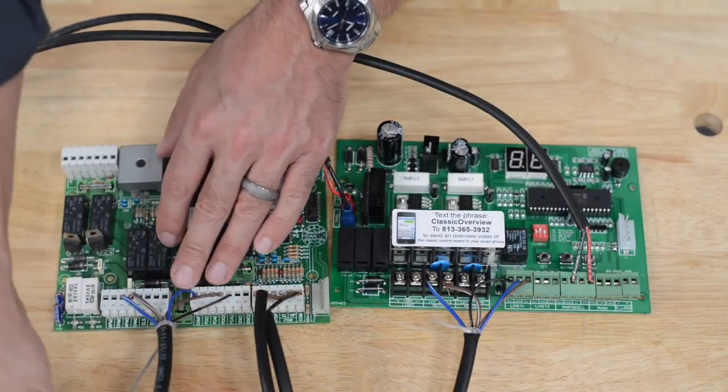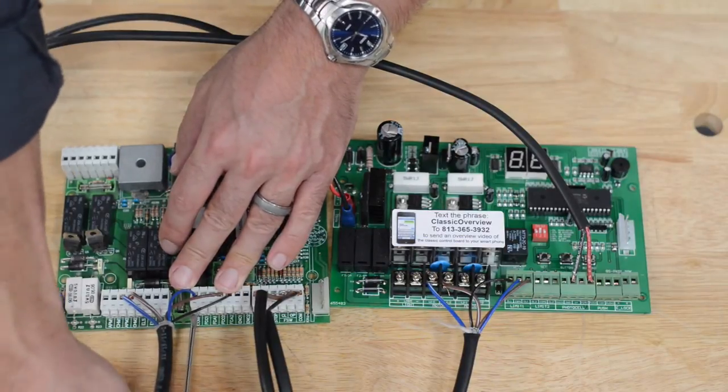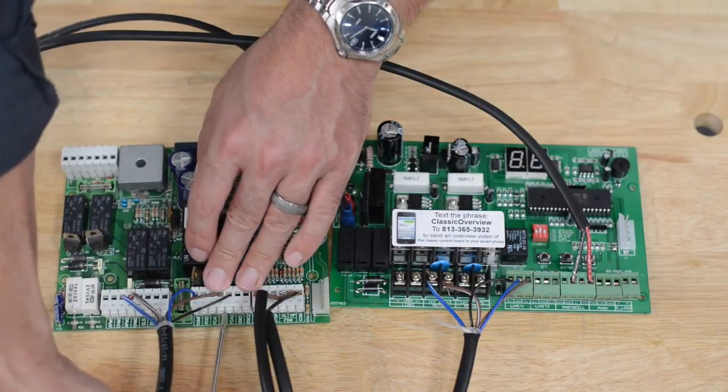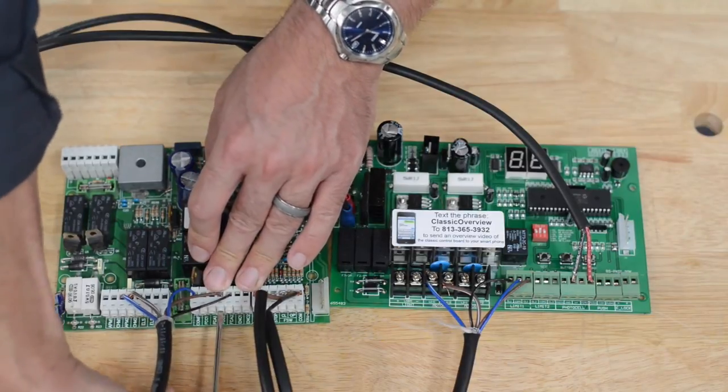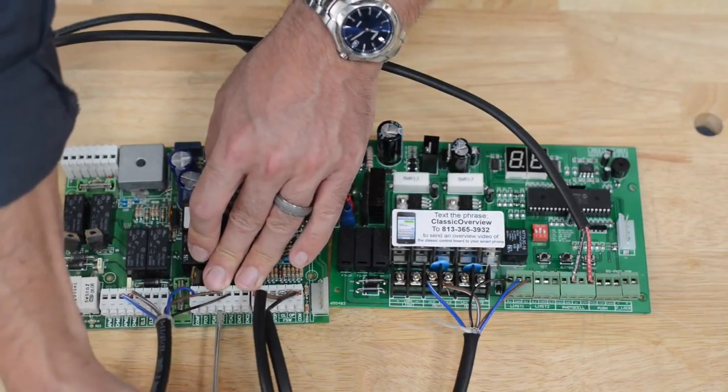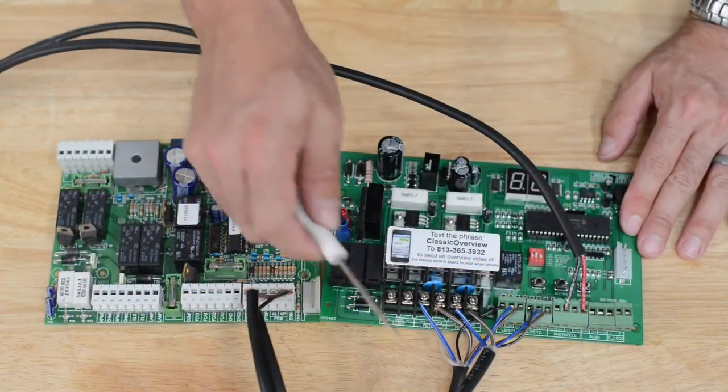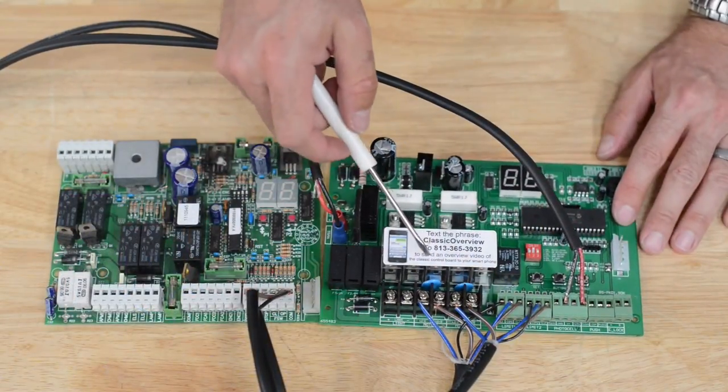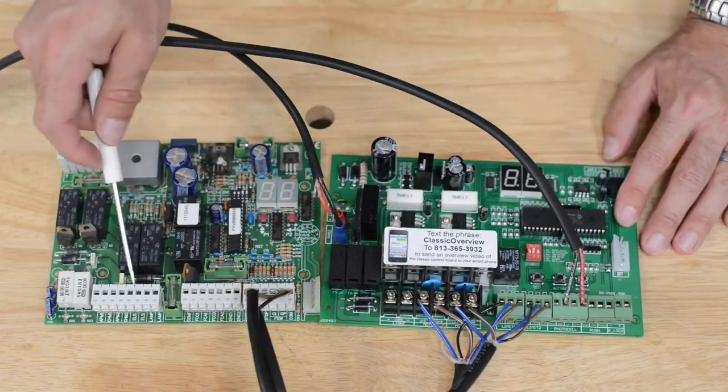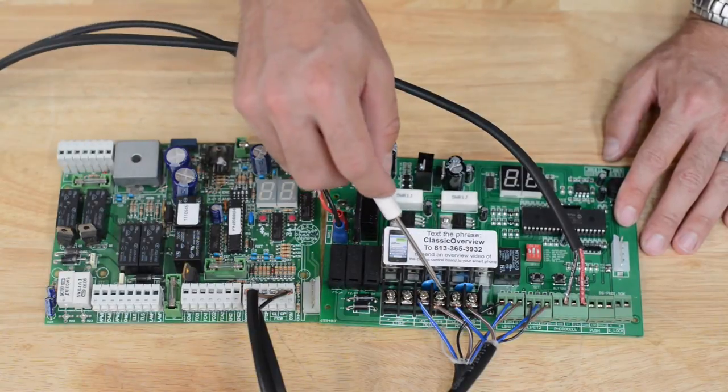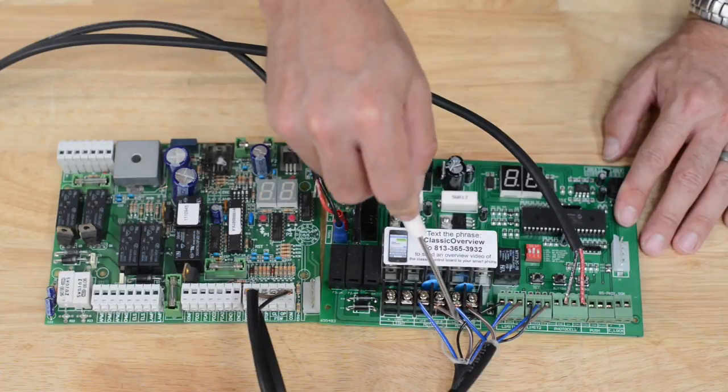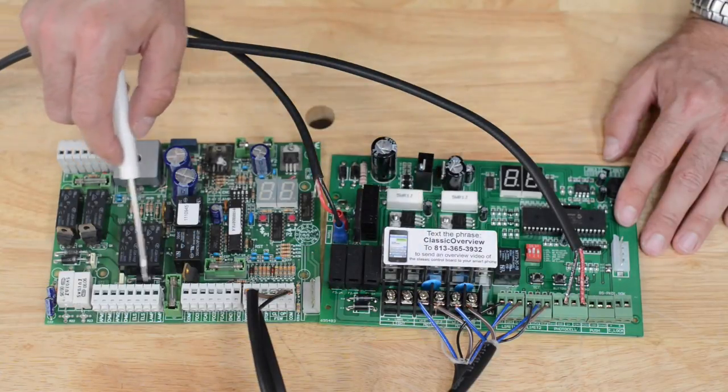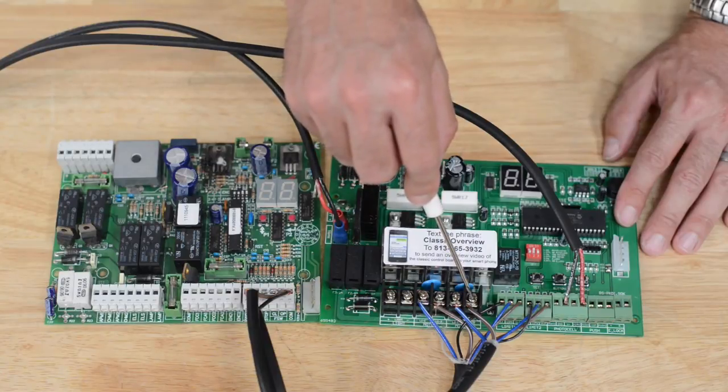The wire colors are going to follow the same pattern that you did with motor one. So we're going to remove from the CN2 and the CN3 block the motor leads and the limit leads. Okay we now have our second motor wired up. And just to run through it again, APM2 will go to L2-1 on the motor two terminal. CHM2 will go to L2-2 on the motor terminal.